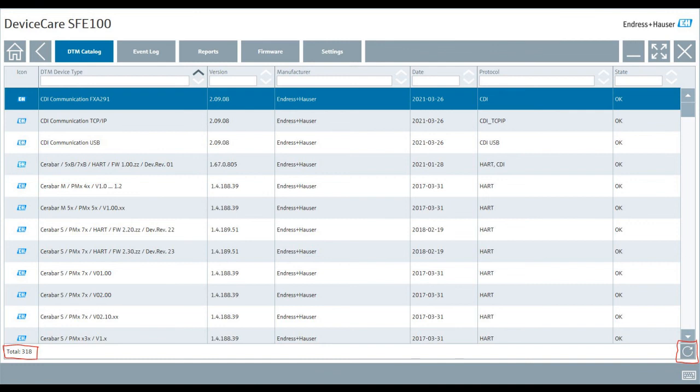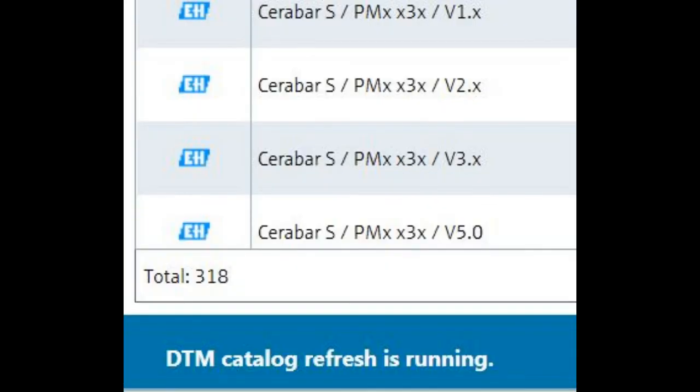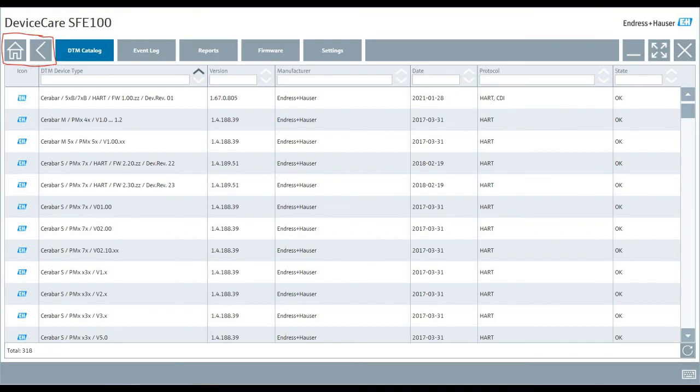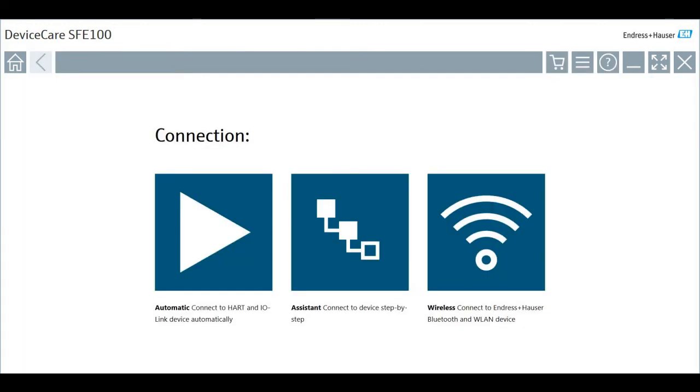My number of DTMs here is 318. I've seen as high as 600 or 800. In either case, what you're going to want to do is hit the Refresh button in the bottom right corner. This will update your DTM catalog. Once you hit that Refresh button, it'll say here, DTM catalog refresh is running. Depending on how many DTMs you have, this might take a few minutes. Once it's done, it'll say the DTM catalog has been applied and you should see here on the bottom left a new number for total DTMs installed. Now you can hit the Back or Home button and that will take you back to the main screen. And you are ready to use Device Care.